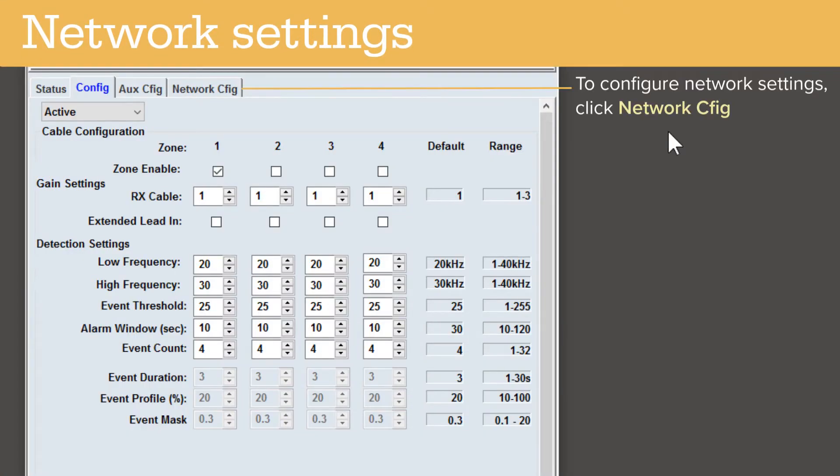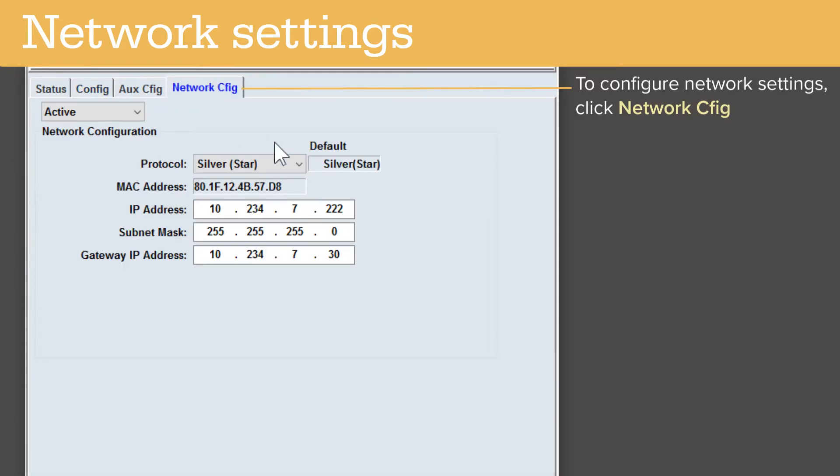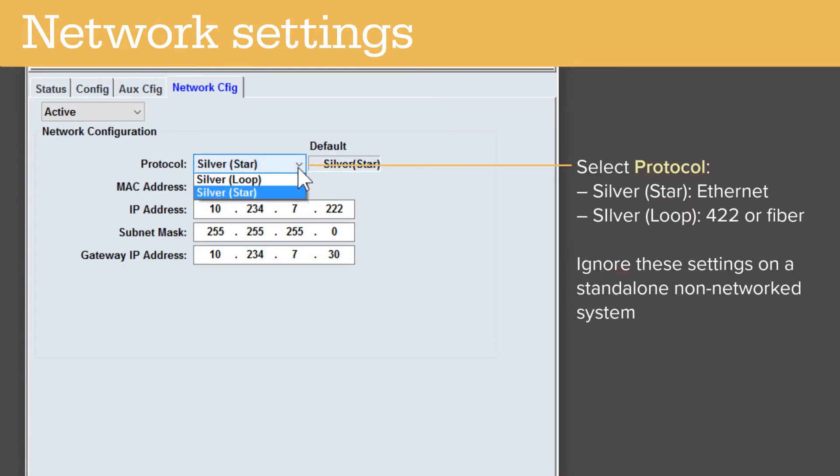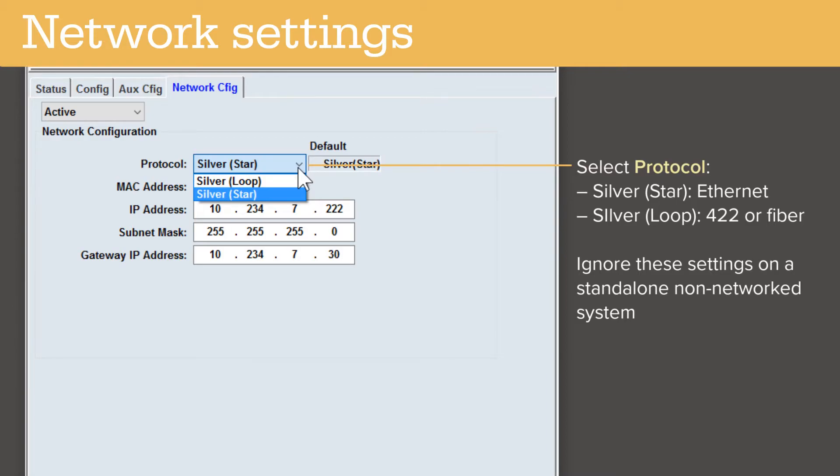To configure the FP400's network settings, click the Network Config tab. If your processor uses an Ethernet connection, select the STAR protocol and enter the IP address information. If your processor uses a fiber or RS422 connection, select Loop. If your processor is not networked, simply ignore these settings.